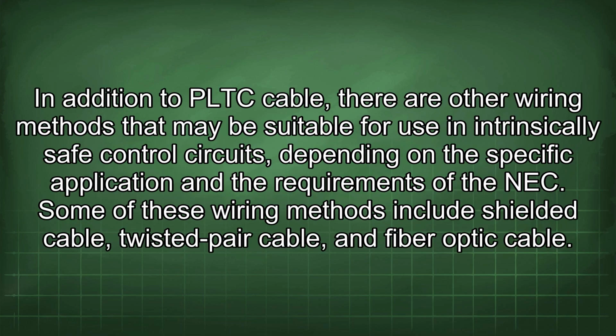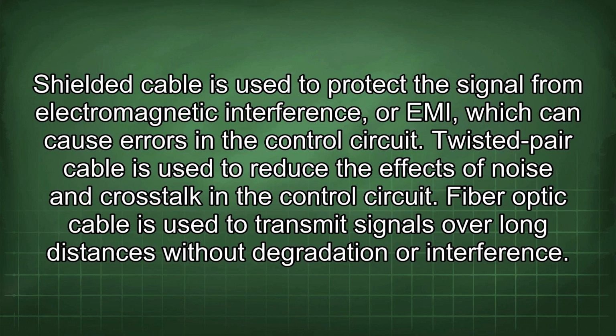In addition to PLTC cable, there are other wiring methods that may be suitable for use in intrinsically safe control circuits, depending on the specific application and the requirements of the NEC. Some of these wiring methods include shielded cable, twisted pair cable, and fiber optic cable. Shielded cable is used to protect the signal from electromagnetic interference, or EMI, which can cause errors in the control circuit. Twisted pair cable is used to reduce the effects of noise and crosstalk in the control circuit. Fiber optic cable is used to transmit signals over long distances without degradation or interference.